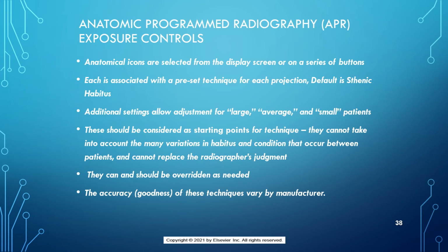Adjust it for habitus, right? There should be a button on there. You should see silhouettes: big patient, little patient, average size patient. Make that adjustment and watch the technique change. Okay? The default setting is sthenic habitus.